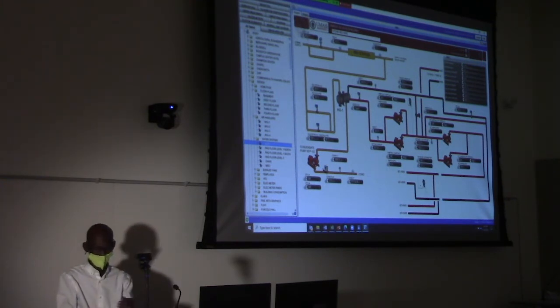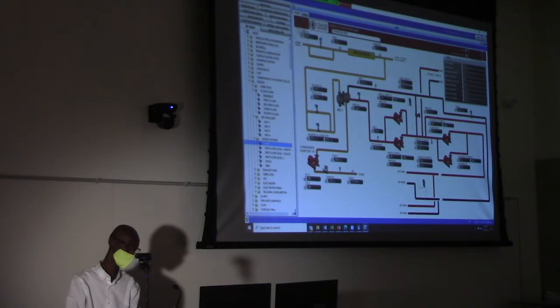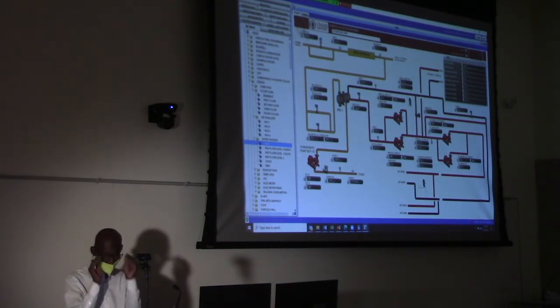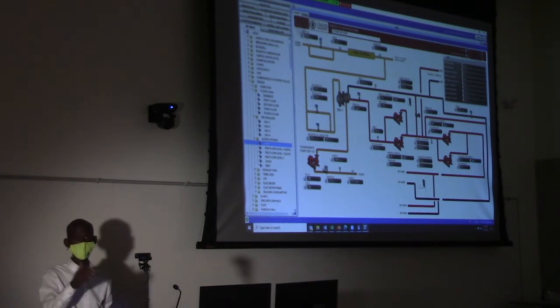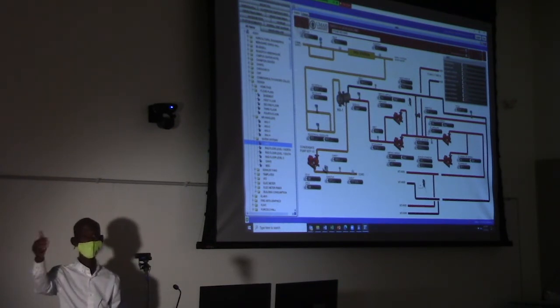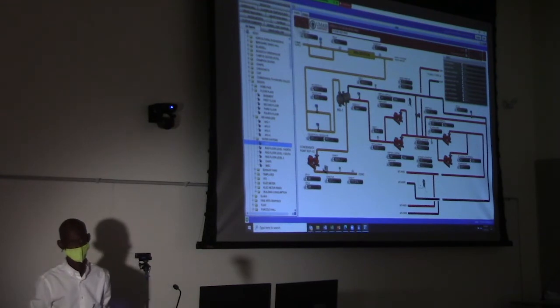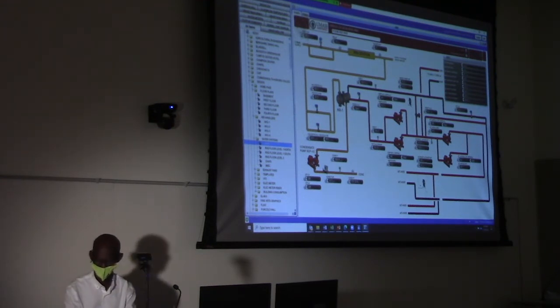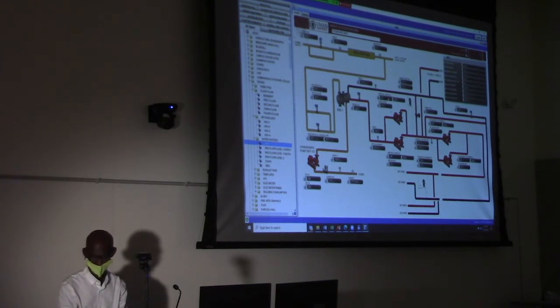So that's why you have two pumps. In case one fails, the other one picks up right away, and vice versa. And also we have alarms on these pumps if there is no flow. We send an alarm to physical plant, and physical plant has to take action right away. But those are the features for the building automation system. I can switch this pump, I can turn this off and turn this on, and vice versa. The way they operate here, you have a lead lag system. So now pump 2A, B is in lag, and 1AB is in lead.